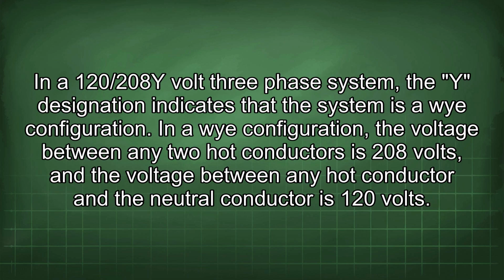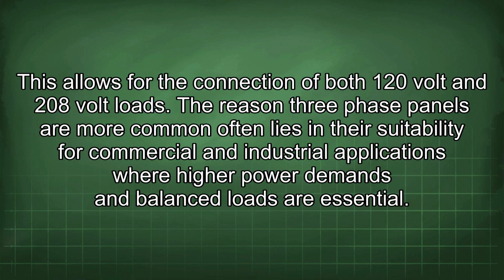In a 120/208 volt 3-phase system, the Y designation indicates that the system is a Y configuration. In a Y configuration, the voltage between any 2 hot conductors is 208 volts, and the voltage between any hot conductor and the neutral conductor is 120 volts. This allows for the connection of both 120 volt and 208 volt loads.